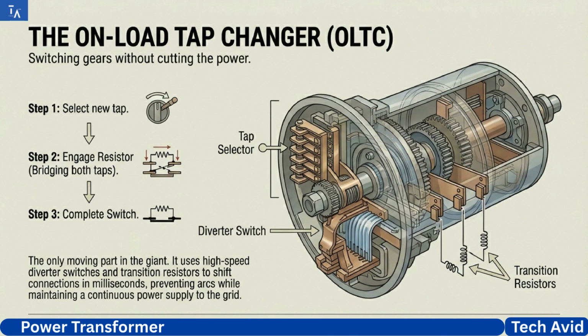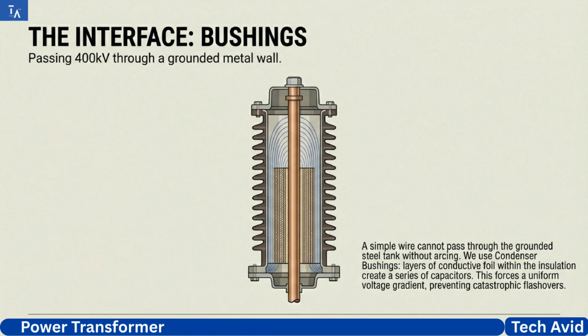But how does 400,000 volts get into the oil-filled tank without flashing over? A simple wire through the grounded steel tank would create a deadly arc. The solution is a condenser bushing. Inside its porcelain shell, layers of conductive foil create a series of capacitors. This forces the insane external voltage to drop in perfectly uniform, manageable steps down to ground potential. It's a voltage ladder.